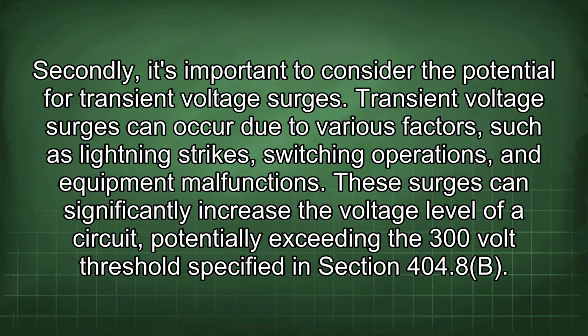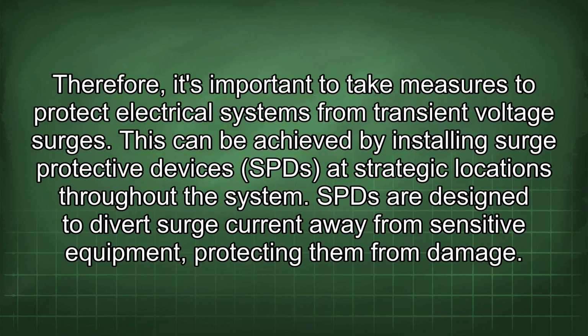Secondly, it's important to consider the potential for transient voltage surges. Transient voltage surges can occur due to various factors such as lightning strikes, switching operations, and equipment malfunctions. These surges can significantly increase the voltage level of a circuit, potentially exceeding the 300 volt threshold specified in Section 404.8b. Therefore, it's important to take measures to protect electrical systems from transient voltage surges. This can be achieved by installing surge protective devices (SPD) at strategic locations throughout the system. SPDs are designed to divert surge current away from sensitive equipment, protecting them from damage.